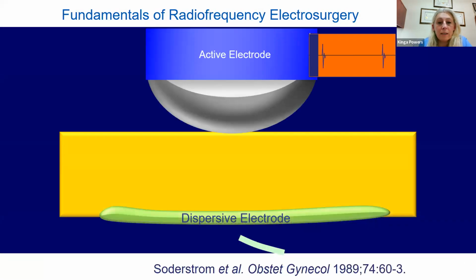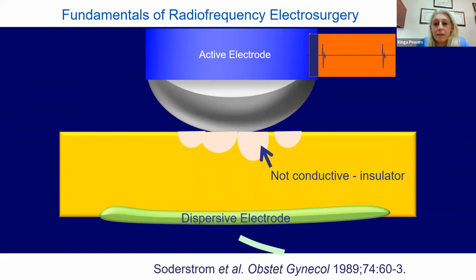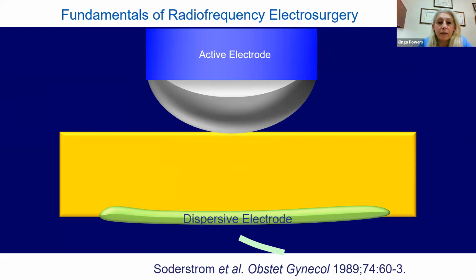To give you an idea of what this looks like: when you use the coag mode, a high voltage output comes out, and when you bring the electrode close to the patient's tissues, you get a superficial zone of desiccation. You see that dark carbonization and think you've sealed the vessel, but it actually acts as an insulator, which subsequently prevents the sealing of the vessel and the transfer of current. So it doesn't work as well as the cut mode.